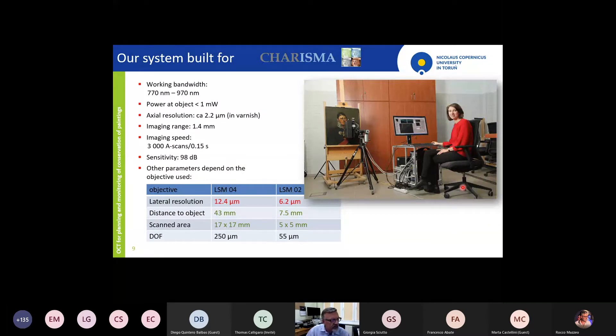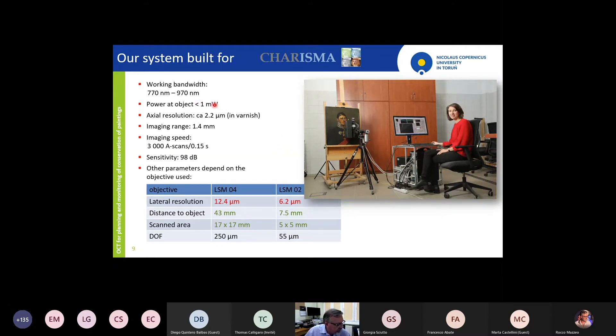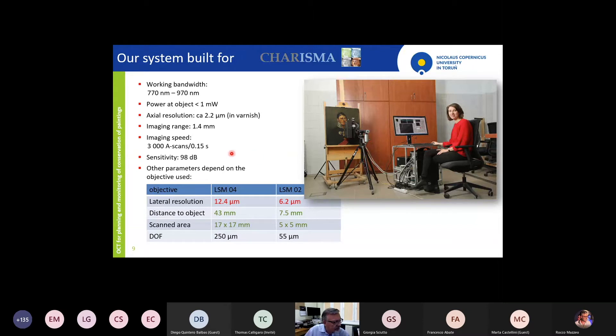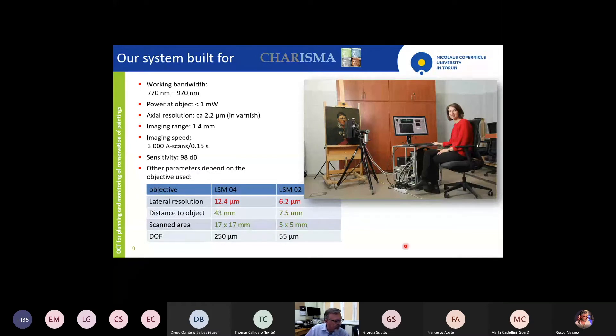This is how our instrument looks — a tripod with the head plus some electronics. What is most important is low-intensity infrared light and actual axial resolution of about two microns in depth, with imaging depth up to one and a half millimeters. The lateral resolution depends on the optics and is a few microns. Importantly, the field of view is rather broad — in our machine up to 17 by 17 millimeters. Of course if we need better resolution we have to compromise and go to a lower field of view.